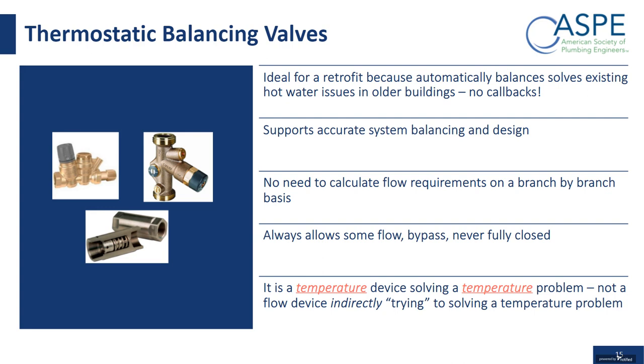So thermostatic balancing valves are ideal for retrofit because they're automatically balancing, solving any existing hot water issues in older buildings. One of the things you'll hear from a lot of project managers at mechanical contractors, the first thing out of their mouths, is no callbacks. They appreciate that you're saving labor on the initial balancing, but they really like that there are no callbacks, because that's the big problem for them when they pull plumbers off a job and then get a phone call because someone's not getting hot water and they have to go back and service it. And that's really one of the big reasons the thermostatic balancing valve started having success.